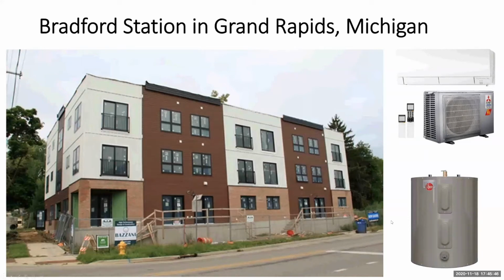I understand heat pump water heaters are only about 3% of sales in the United States, so most people have never bumped into one. But my developments since 2008 have been all electric, 100% solar powered, and there's not enough roof space to do electric resistance water heaters and 100% solar power unless it's just a one-story building. But as soon as you get to 2 or 3 stories, you need to move to a heat pump water heater because water heating is usually the number one load in an apartment.